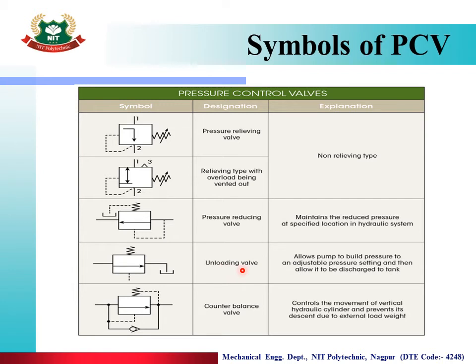Unloading Valve symbol: system pressure comes from inlet port 1; port 2 goes to tank. A drain line from the system shifts the valve line, compressing the spring and allowing flow to tank. It allows the pump to build pressure to an adjustable pressure setting and then discharge to tank. Counterbalance Valve is similar to a pressure relief valve but includes a check valve, and it prevents descent due to external load weight.